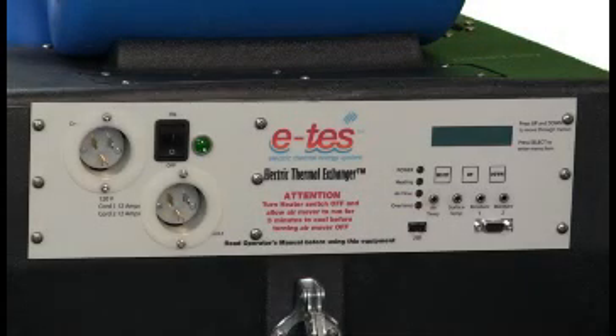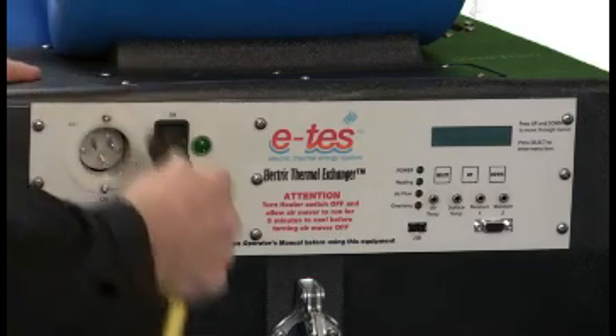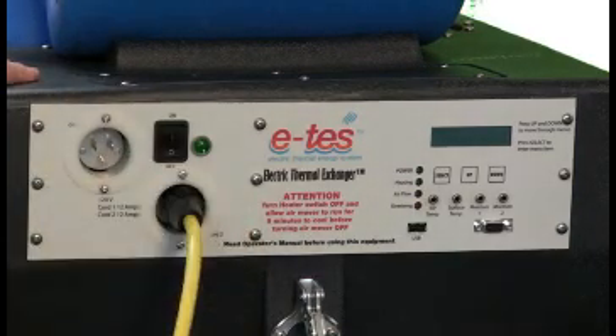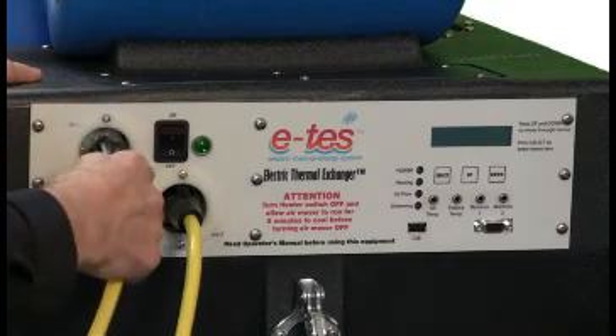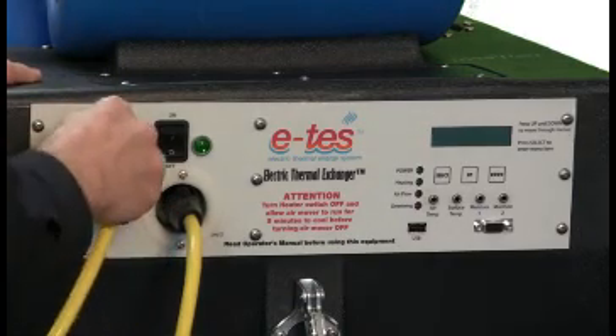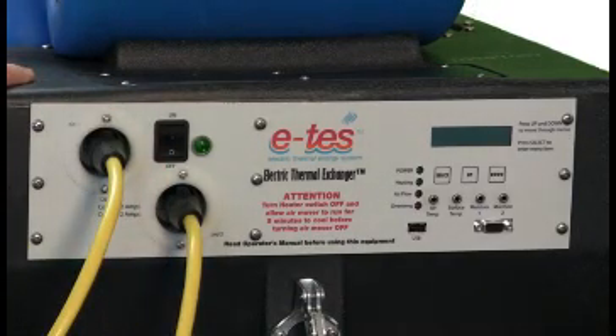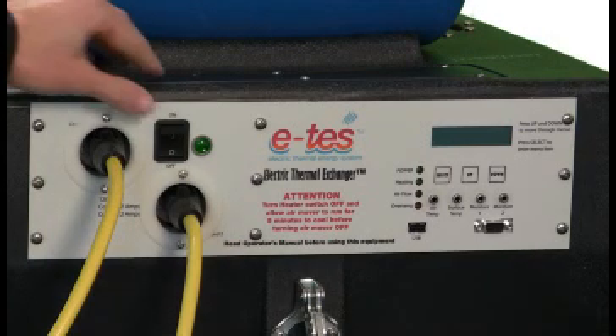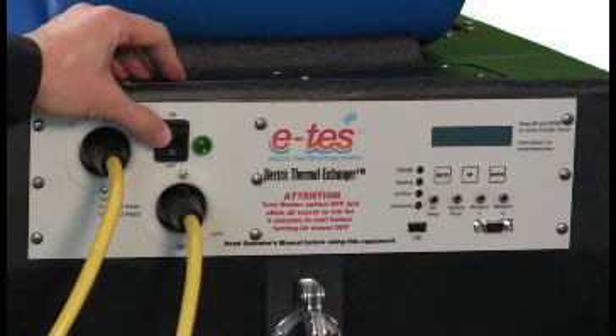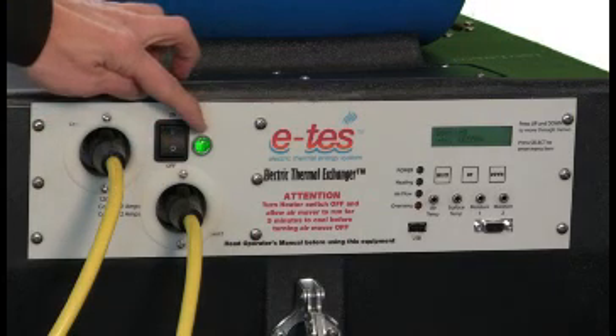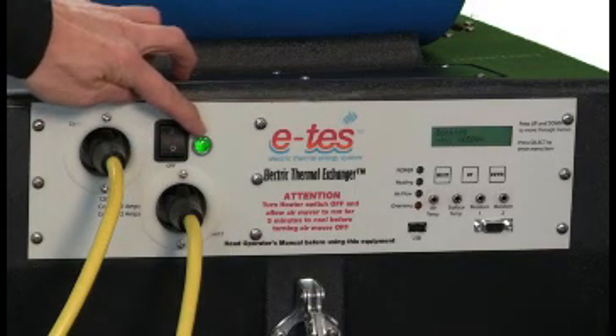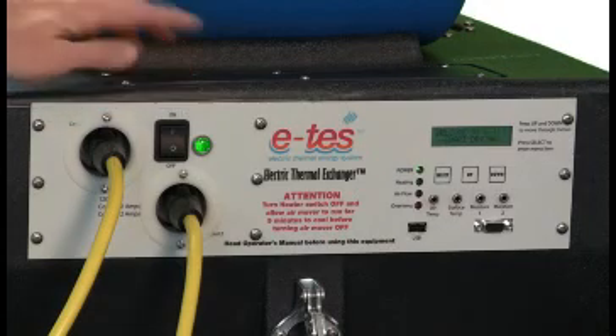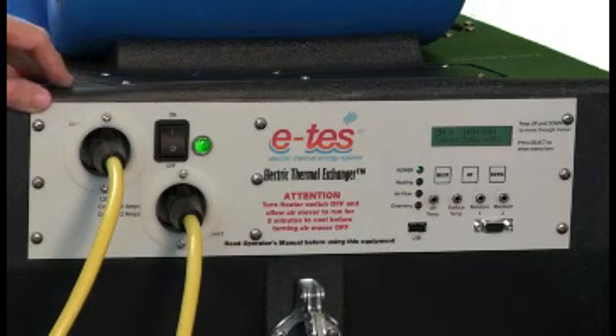With the 120 volt E-Tes SD, there are two power cords that must be connected. Simply plug your cords into the wall outlet and then connect the cords to the E-Tes unit. The amp draw of the unit requires that each cord be on separate circuits. When you turn the power switch on, the green light will indicate if you are on separate circuits. If the green light lights, you are on two separate circuits and you're ready to go.